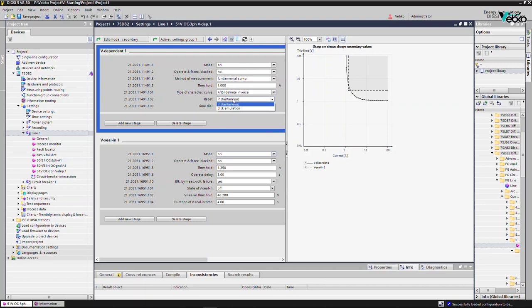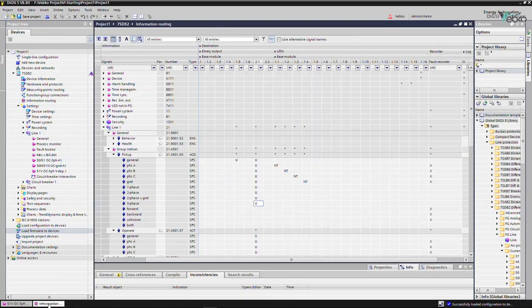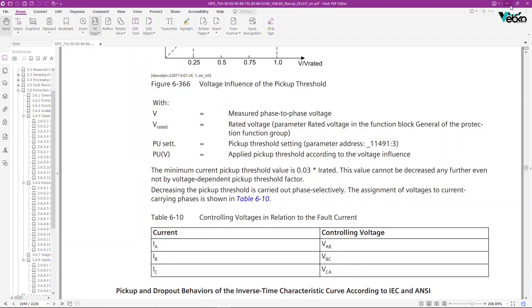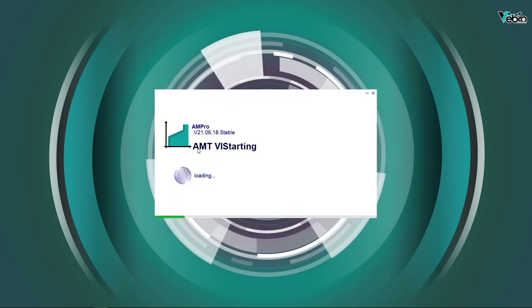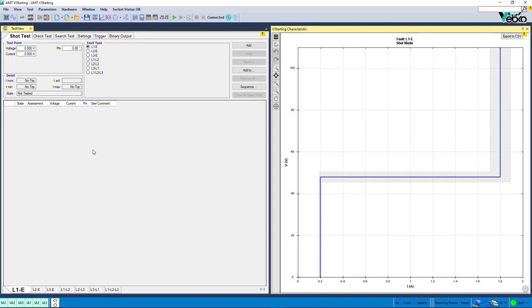For the reset parameter, you can select the instant reset option or reset by modeling the movement of disk relays. The time dial option also allows moving the characteristic in the direction of the time axis. The next stage considering under-voltage function conditions is also set so that if there are sufficient voltage conditions, the activation of the function is seen. After applying the settings on the relay and specifying the required contacts in the configuration section, it is time to test the function. Keep in mind that due to the curve performance, either use the pickup contact or consider the time required in the max fault time section for the 51V function performance.